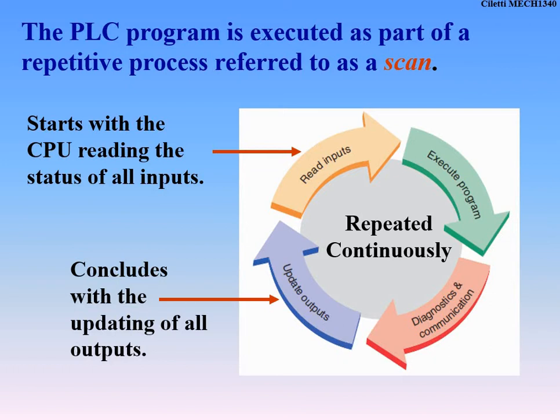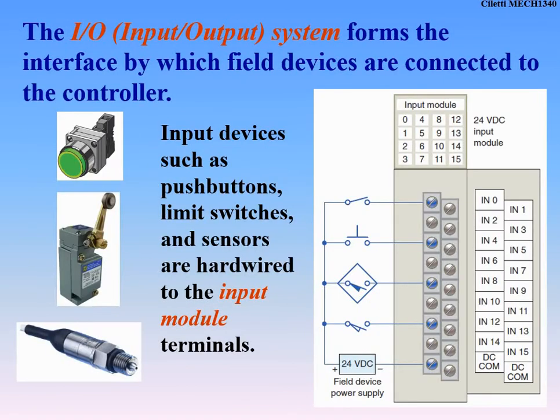This is on a test as well. Here's what a PLC is constantly doing once you turn it on — this is all it does. It sits here and scans and goes through this cycle. It reads all the inputs so it knows where everything is and what needs to happen. Then it goes through the ladder logic, executes the program, communicates, and updates all the outputs based on the inputs as it executes through each rung. Then it starts all over and reads the inputs again — constantly sitting there scanning, waiting for something to happen.